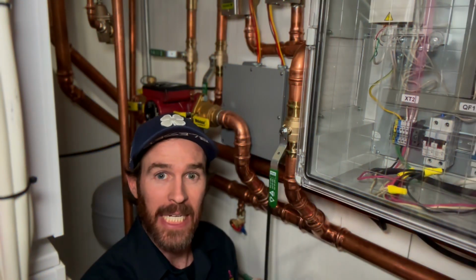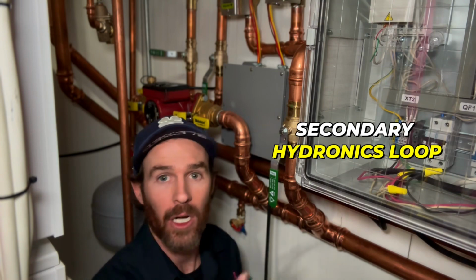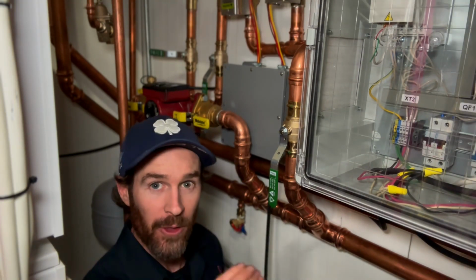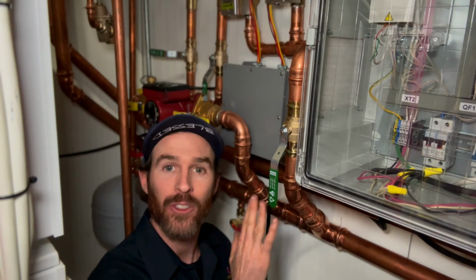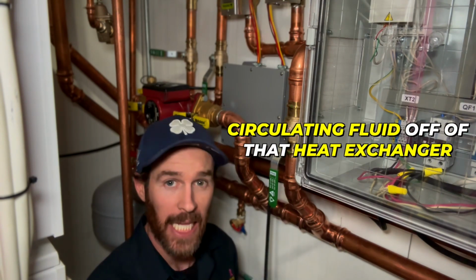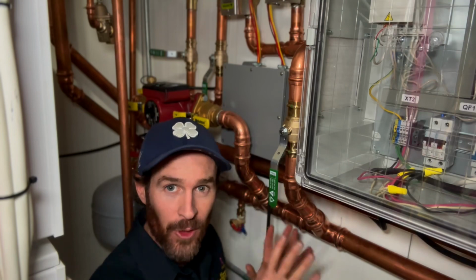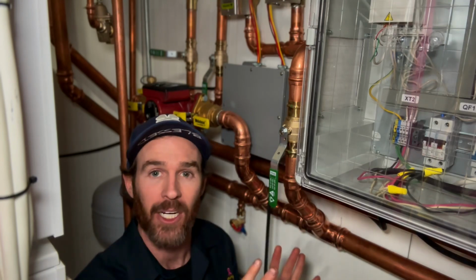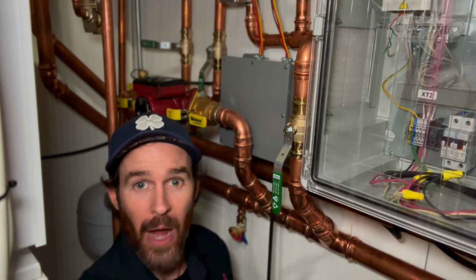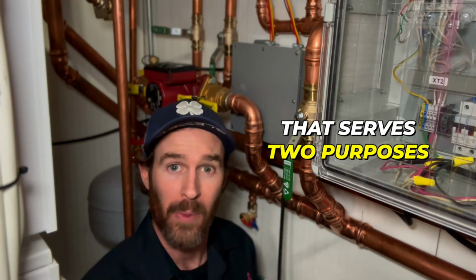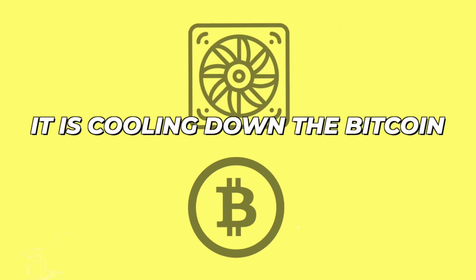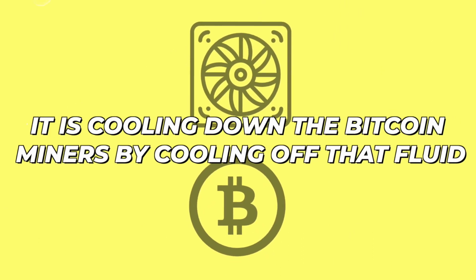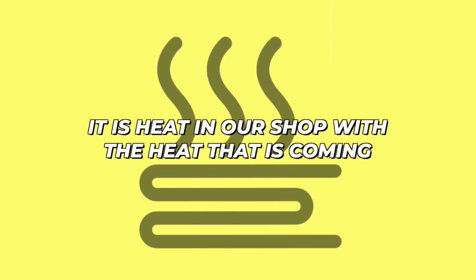This is part 3, the secondary hydronics loop. Remember that flat plate heat exchanger I showed you? The other side of that loop is right here, circulating the fluid off of that heat exchanger through these pipes. These pipes run through a forced air hydronics coil inside an air handler that serves two purposes: cooling down the Bitcoin miners by cooling off that fluid, and heating our shop with the heat coming out of that fluid.